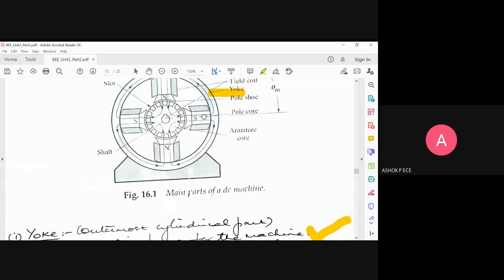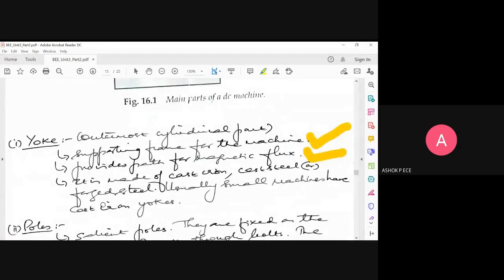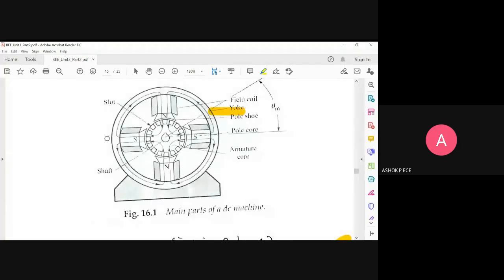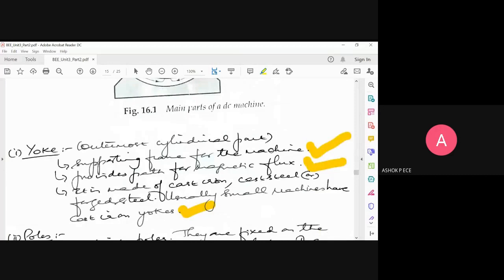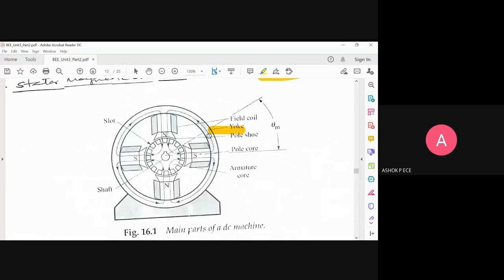The yoke is made up of cast iron, cast steel, or forged steel, and must be strong enough to withstand the motor in tough conditions. Small machines have cast iron yokes; large machines have cast steel or forged steel yokes. Just like the transformer has a container holding the entire transformer, the DC motor is held by this large cylinder called the yoke, which provides support and a path for magnetic flux.